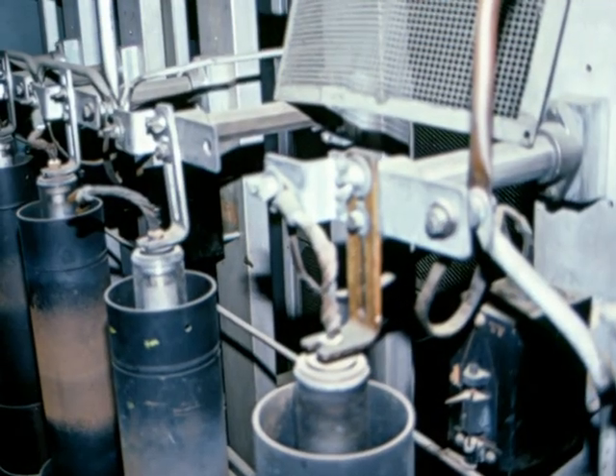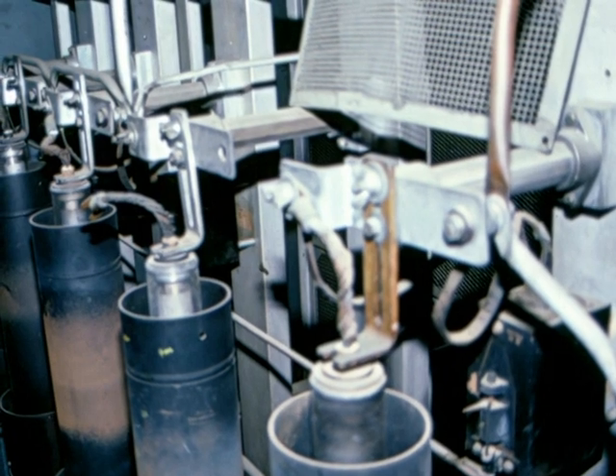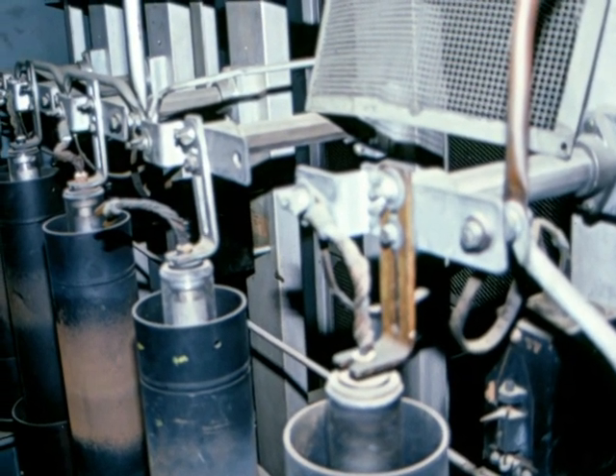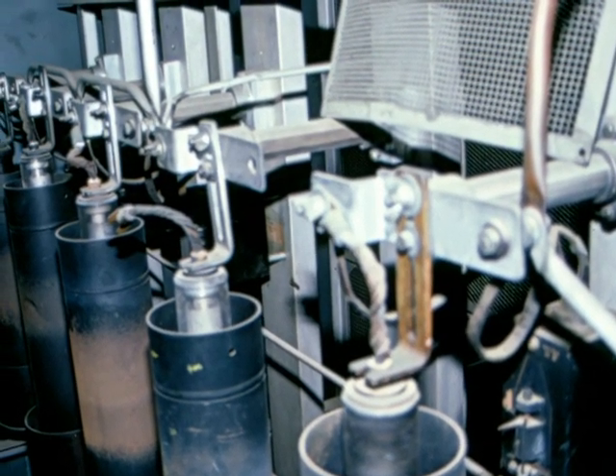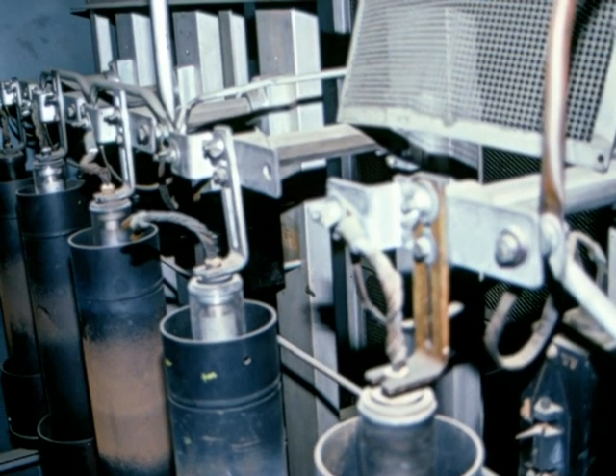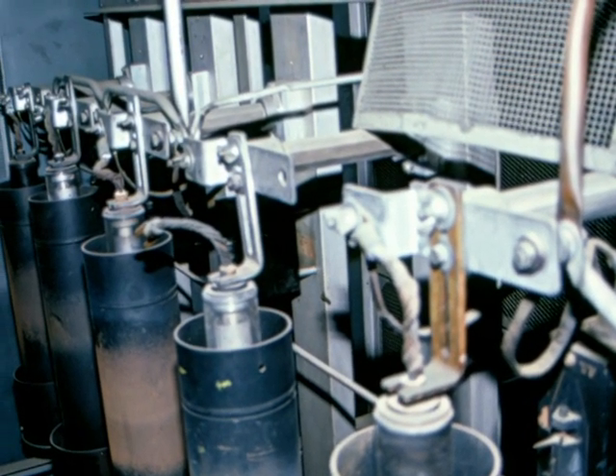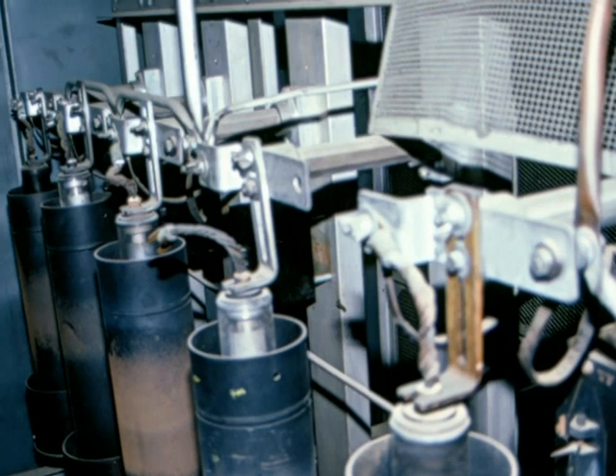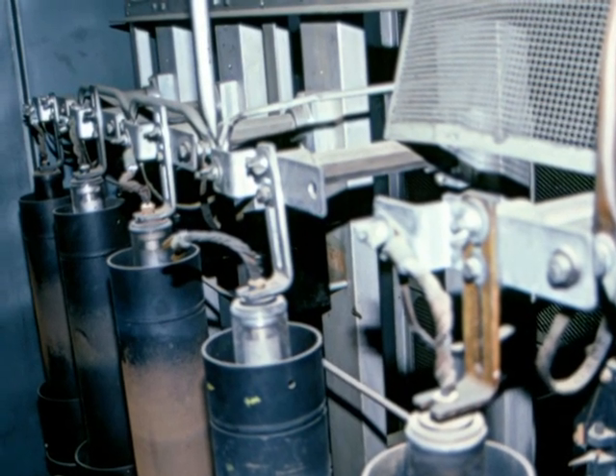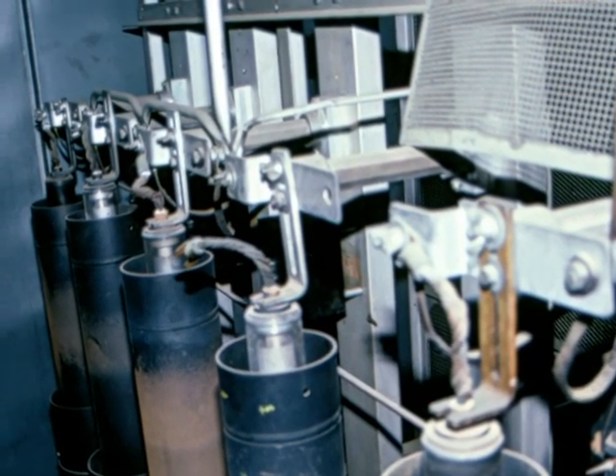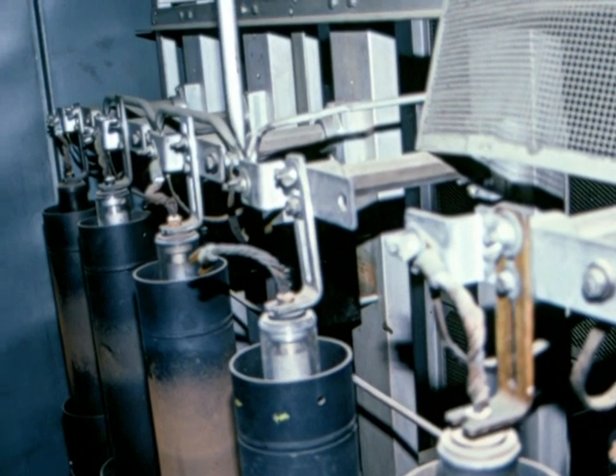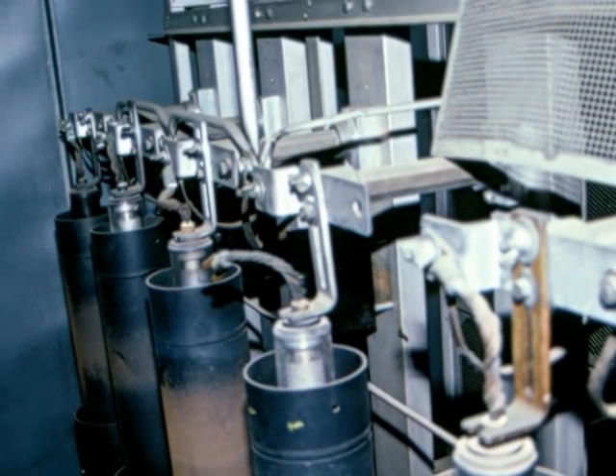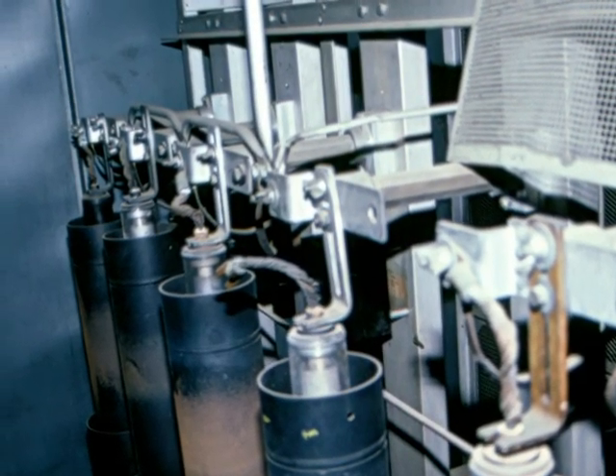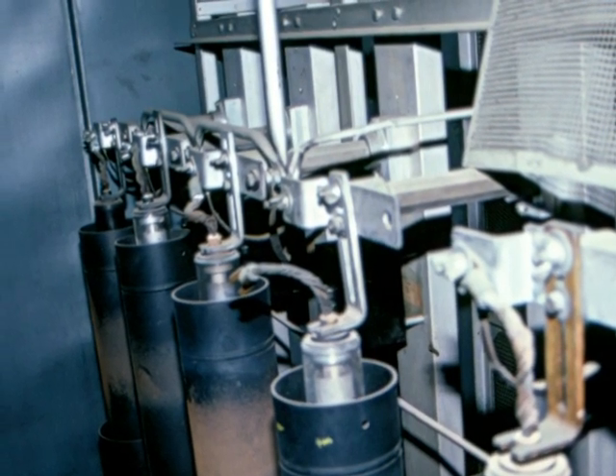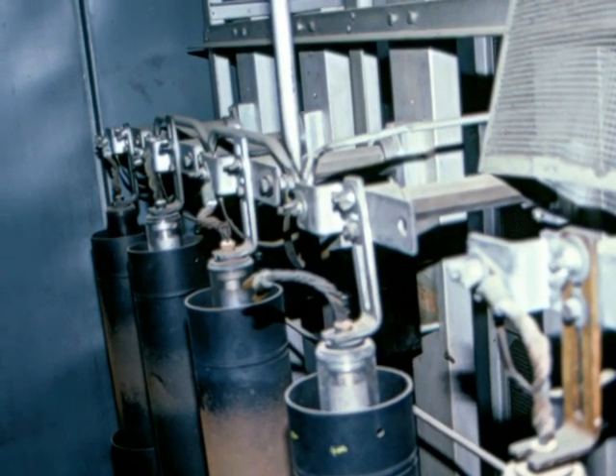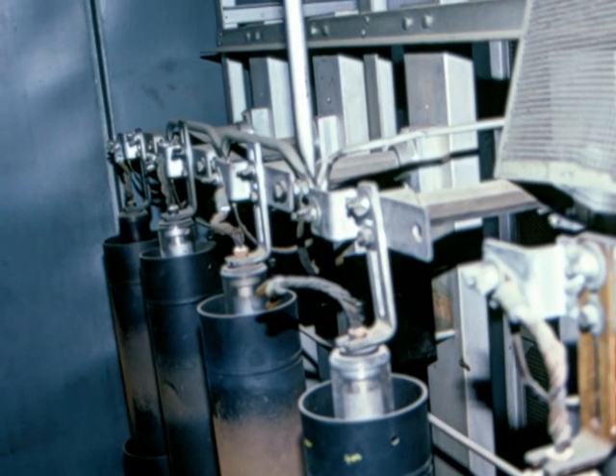The glass 870 rectifier tubes were replaced with metal 870A tubes for better cooling and longer life. These were rated at 15,000 volts and 60 amperes. Their filaments were single-phase, 5 volts at 65 amperes. Frequently, these tubes would arc back. The best estimate of the peak inverse surge current during the arcing was 4,000 amperes. These arcbacks would be felt over the entire electric power network.